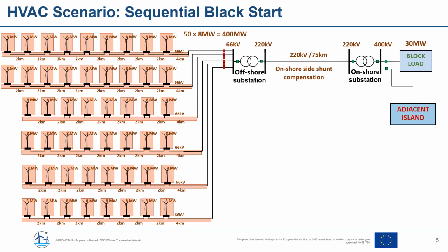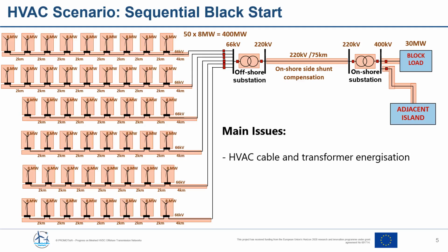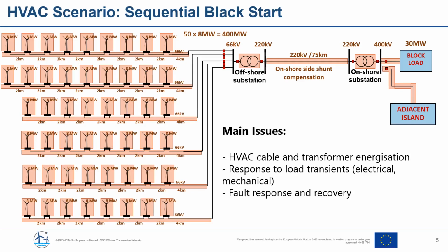And then we will energize the offshore substation, the HVAC export cable, and the onshore substation. So once we have the onshore substation energized, we can actually power up local block loads and finally connect to adjacent islands just to continue with the service restoration process. The main issues are HVAC cable and transformer energization, response to load transients, and fault response and fault recovery.